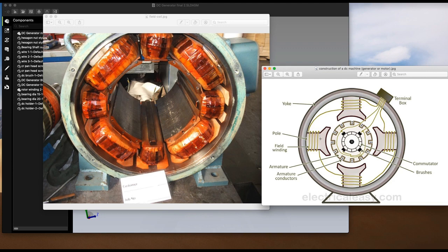The pole core and the pole shoe are fixed to the magnetic frame by bolts. Usually the pole core and shoes are made of thin cast steel or iron laminations which are riveted together under hydraulic pressure. The poles are laminated to reduce eddy current loss.